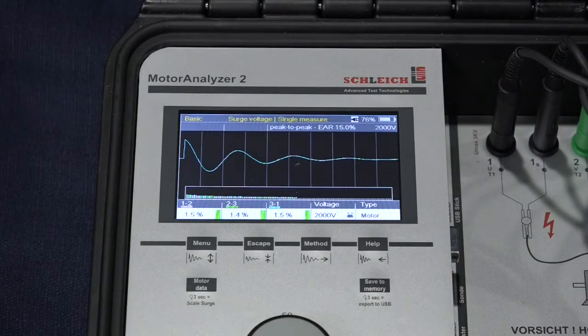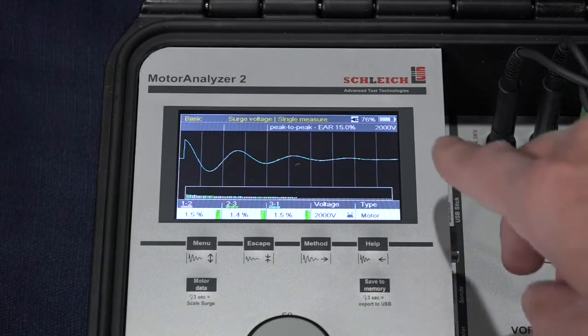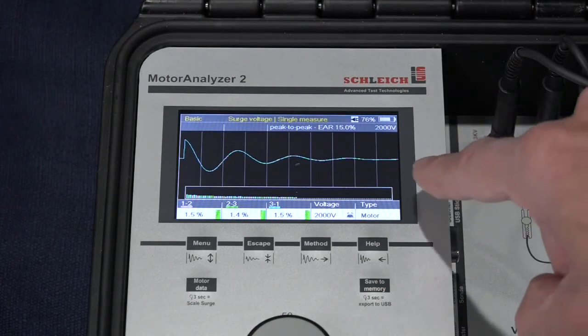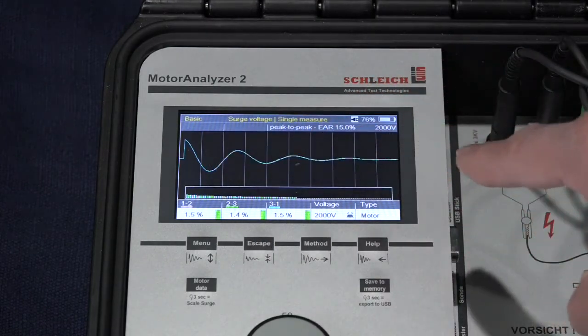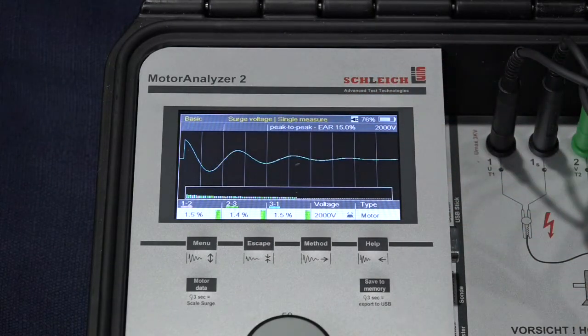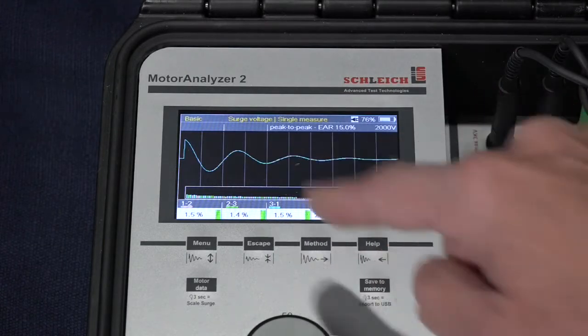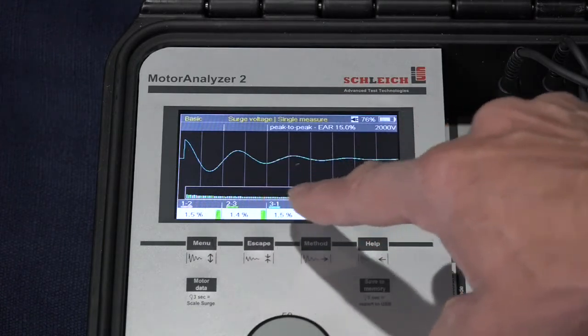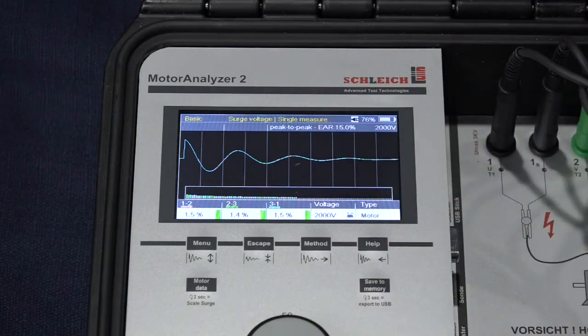So there are the 3 waveforms at our final test voltage of 2000 volts, and we can see we have 3 waveforms basically all on top of each other, and that's a good thing. If we had had an arcing turn-to-turn fault, we'd have seen one of them shifted, and in this bar graph of the EAR values, one of them would have jumped up quite high.